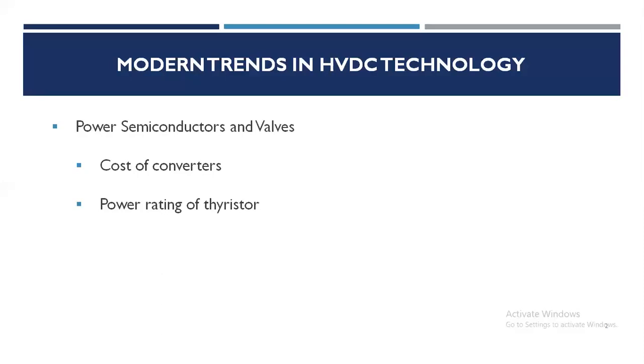In contrast, the IGBT, that is insulated gate bipolar transistor device, requires much less power to turn off and has high switching speeds. IGBT converters are available at plus minus 150 kV and 350 MVA rating. Switching speeds up to 2 kHz are feasible.